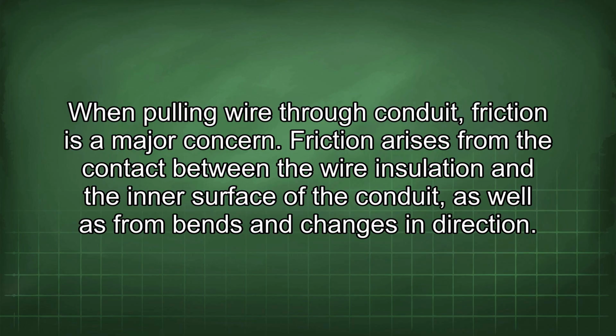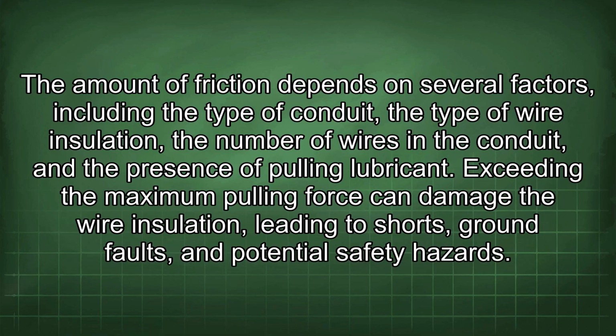When pulling wire through conduit, friction is a major concern. Friction arises from the contact between the wire insulation and the inner surface of the conduit, as well as from bends and changes in direction. The amount of friction depends on several factors, including the type of conduit, the type of wire insulation, the number of wires in the conduit, and the presence of pulling lubricant. Exceeding the maximum pulling force can damage the wire insulation, leading to shorts, ground faults, and potential safety hazards.